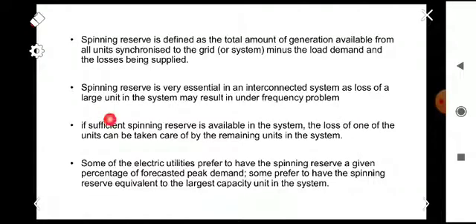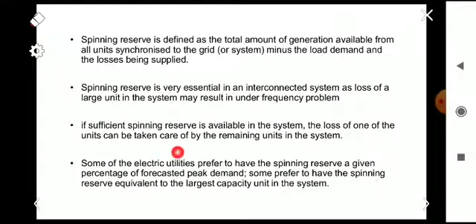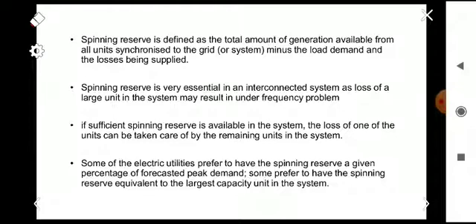Spinning reserve is very essential in an interconnected system, as the loss of a large unit may result in an under-frequency problem. If sufficient spinning reserve is available, the loss of one unit can be taken care of by the remaining units. If any unit is disconnected from the system due to a fault, the remaining units can take care of the available loads using the spinning reserve.